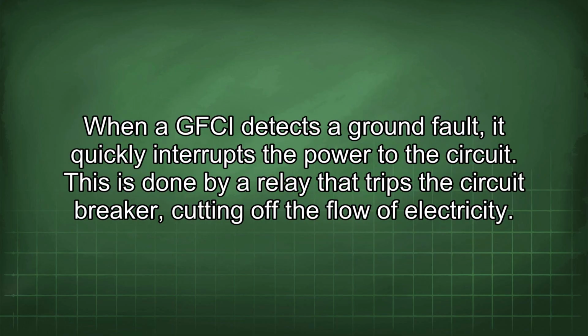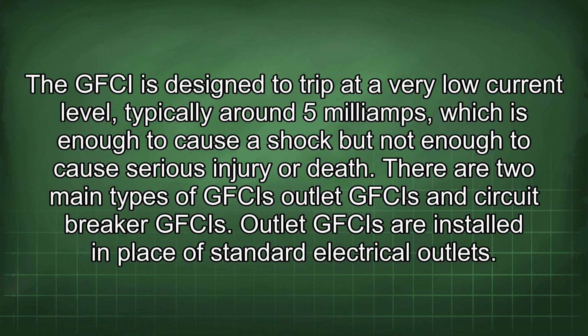When a GFCI detects a ground fault, it quickly interrupts the power to the circuit. This is done by a relay that trips the circuit breaker, cutting off the flow of electricity. The GFCI is designed to trip at a very low current level, typically around 5 mA, which is enough to cause a shock but not enough to cause serious injury or death.